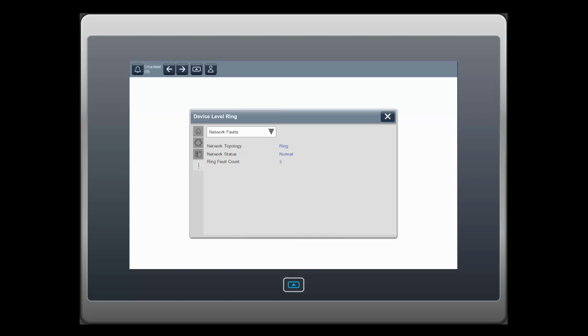The most common fault, the ring fault, usually occurs when one or more links is broken, or a node is taken off the network. An unexpected loop detected fault occurs when the network ring was closed without defining at least one node as a supervisor in linear topology. A partial network fault occurs when the active ring supervisor detects a network fault in one direction only.